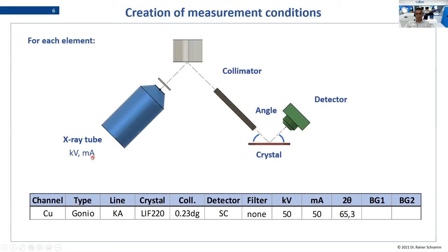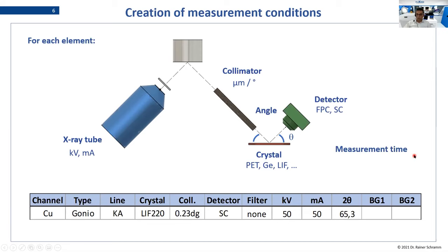Now we have to talk about the parameters we need to adjust. On the tube side it's the voltage and the milliamps. On the collimator side it's the distance of the blades — how much radiation you want to let through. Then of course the crystal, which has to correspond to the wavelengths you want to reflect to the detector. Then we have the angle used for the reflection, and of course the detector type. We also need to define the measurement time — how long you keep that arrangement and register your intensity as counts. The atmosphere — vacuum or helium — also influences your measurement result.